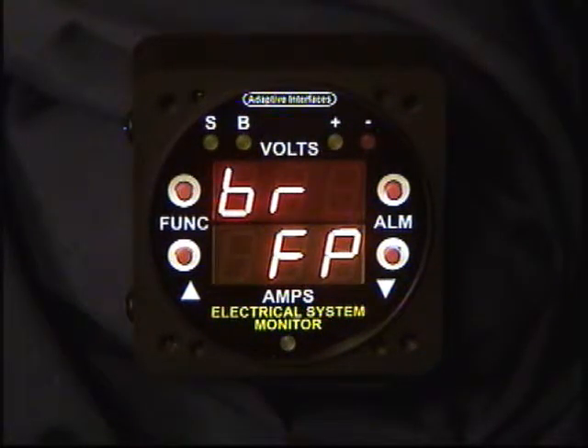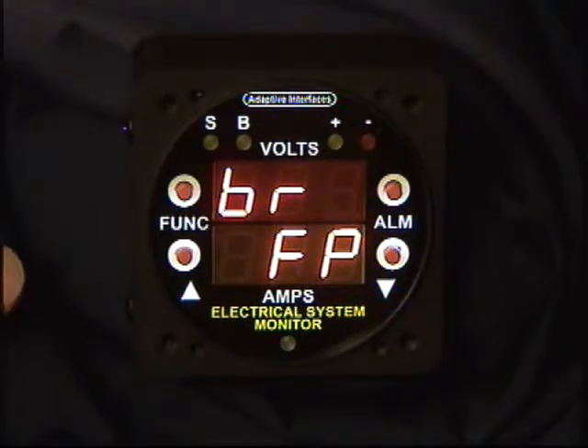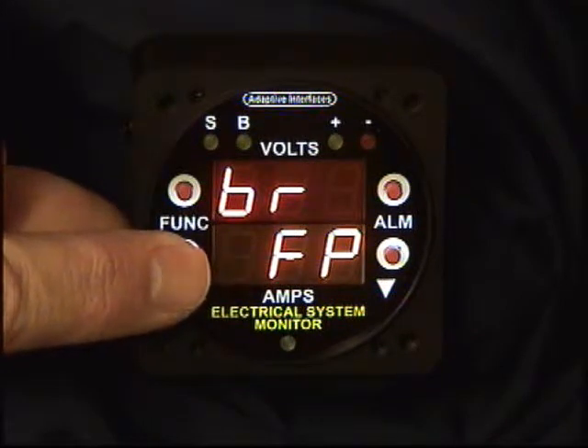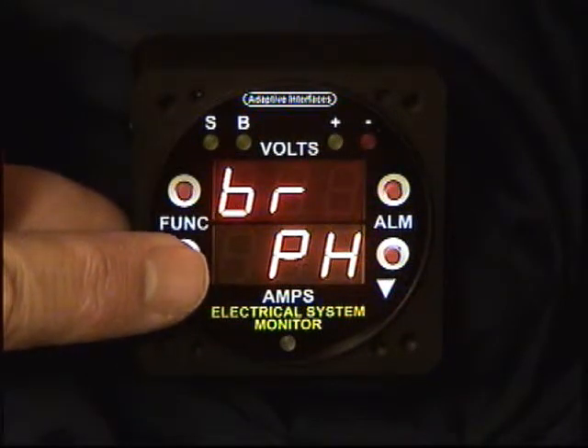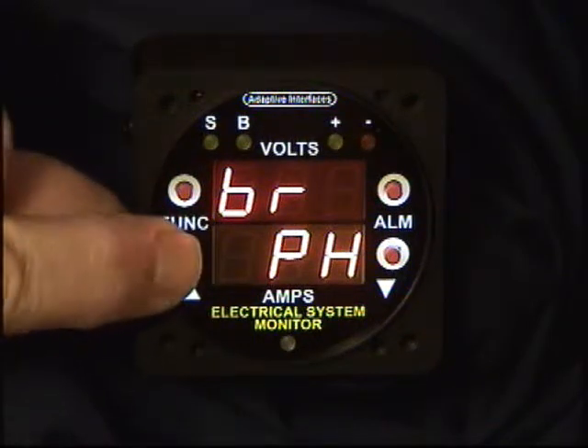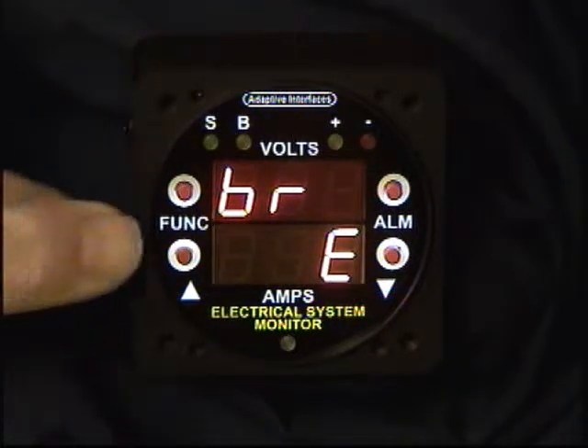Now we are in menu level 1. The functions available in menu level 1 include a brightness function which controls the display brightness of the digits and the LEDs. Right now it's being controlled by the front panel. You have choices of front panel, a photo cell on the front of the instrument, and also an external voltage source — for example, a potentiometer on the instrument panel to adjust display brightness.